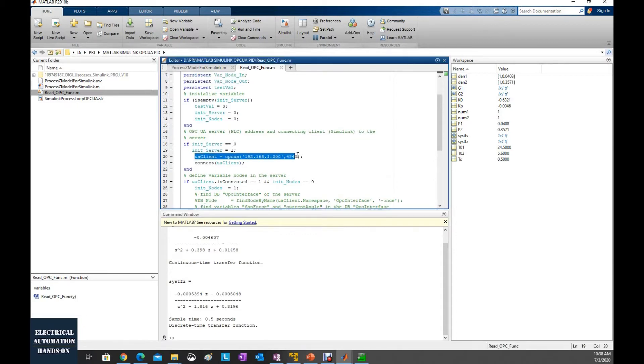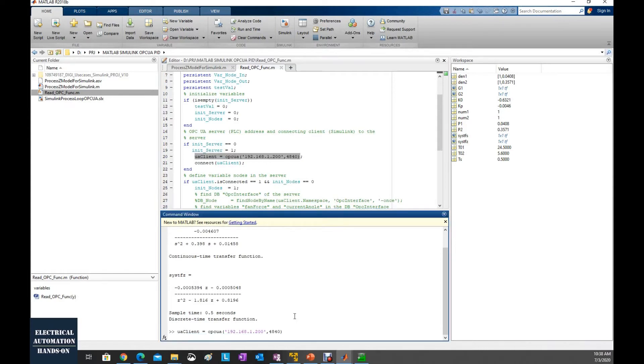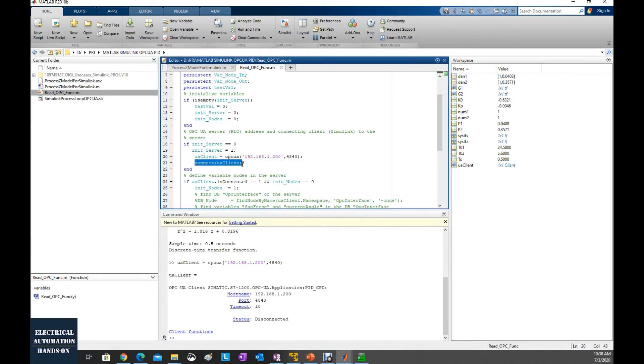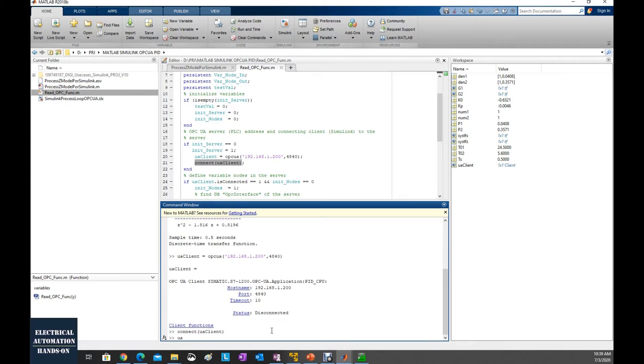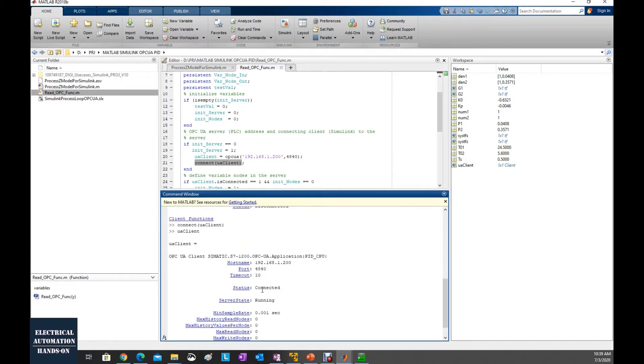From here, we can copy this line and paste it into the command window. After running it, we can check out the connection status — currently the connection is disconnected. Then we type in the connect command to connect this connection. After this, let's type in the UA client to see the actual status. Now it shows the UA client is connected, which means this OPC UA client from MATLAB is already connected to our OPC UA server on the PLC.